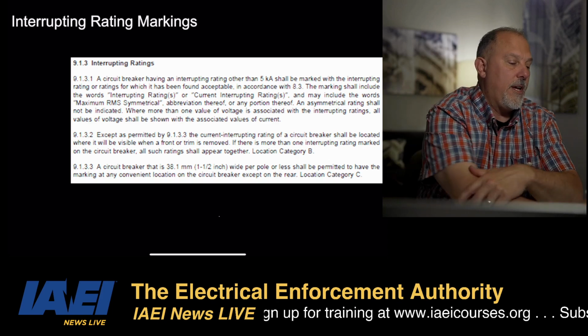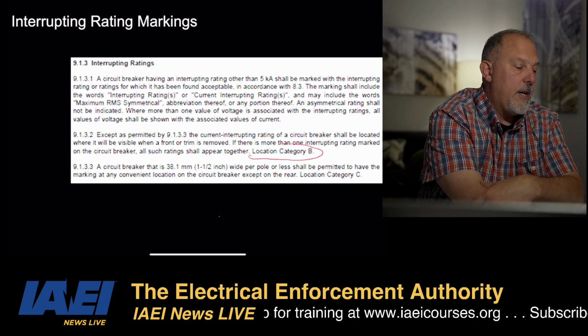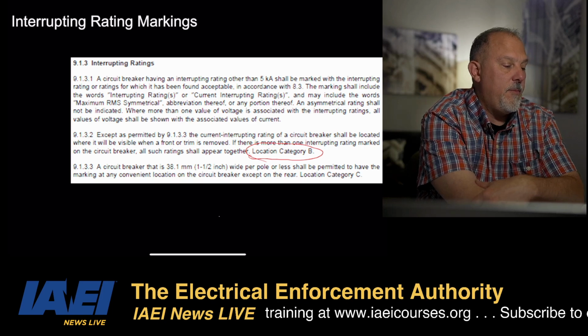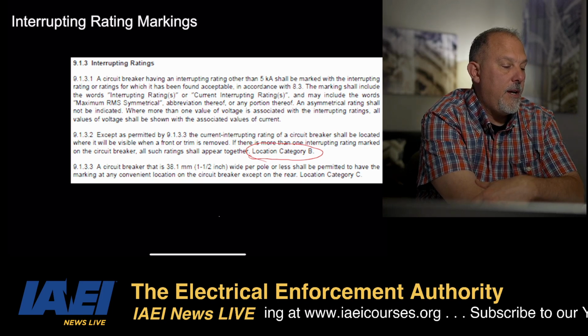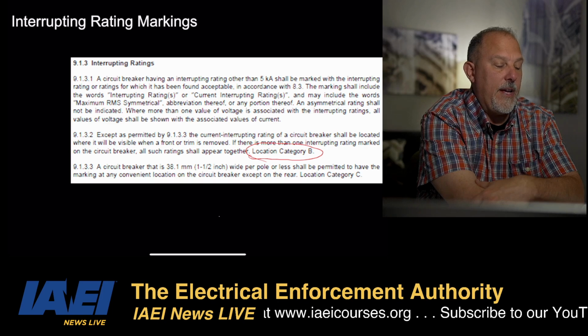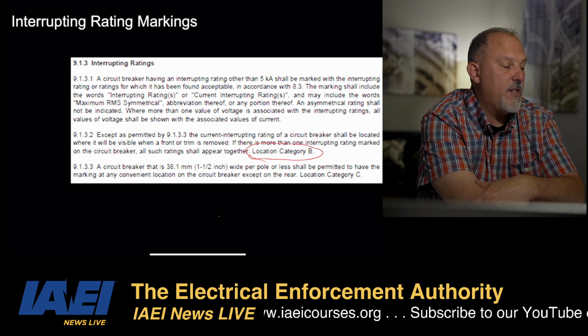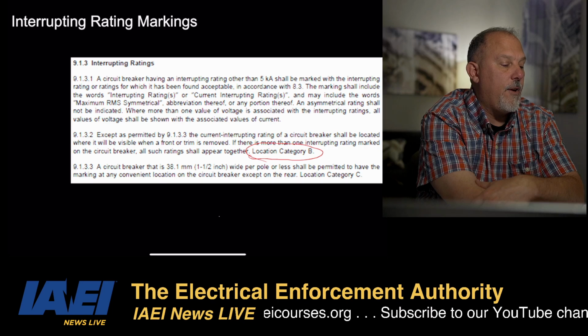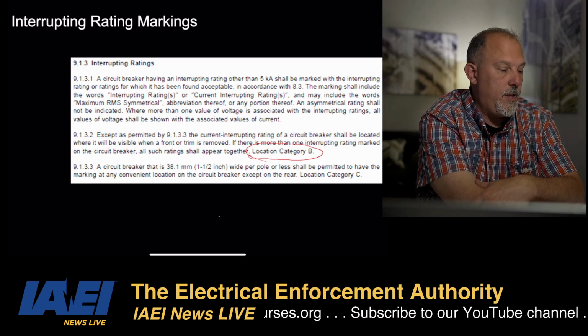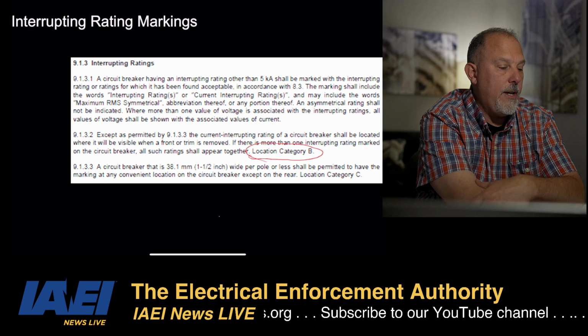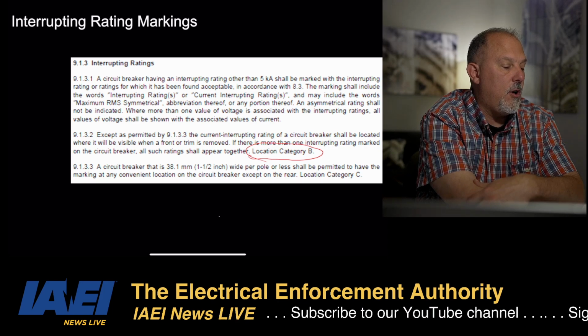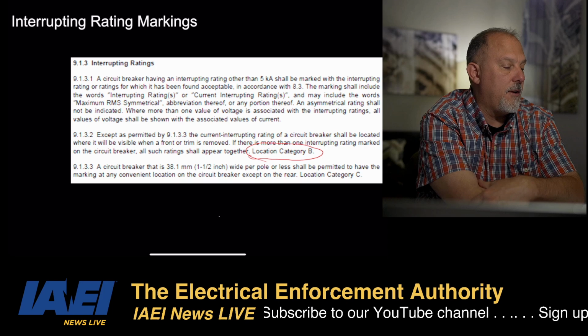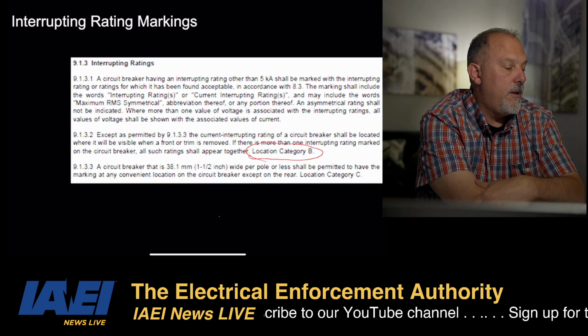We're looking for a location. There it is. Location category B. Except as permitted, the current interrupting rating of a circuit breaker shall be located where it will be visible when a front or trim is removed. If there is more than one interrupting rating marked on the circuit breaker, all such ratings shall appear together.